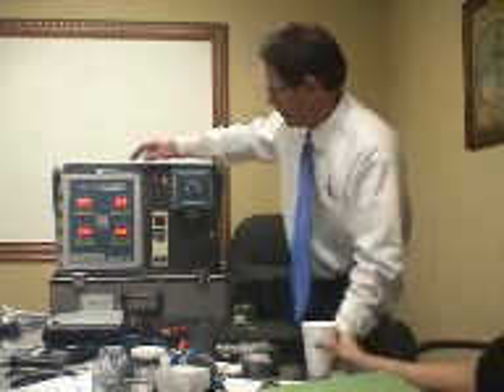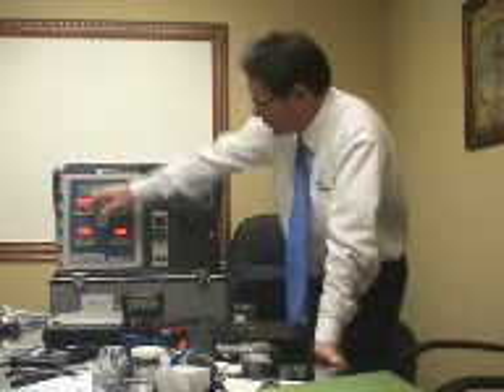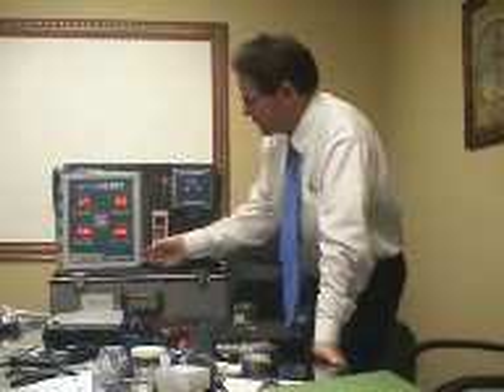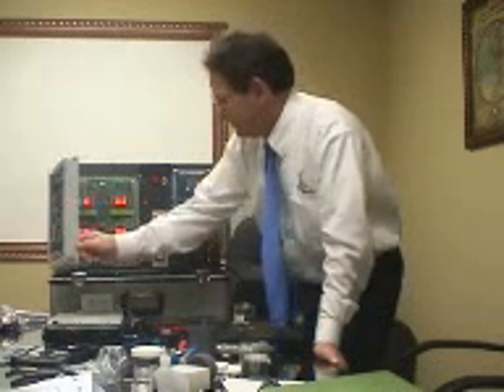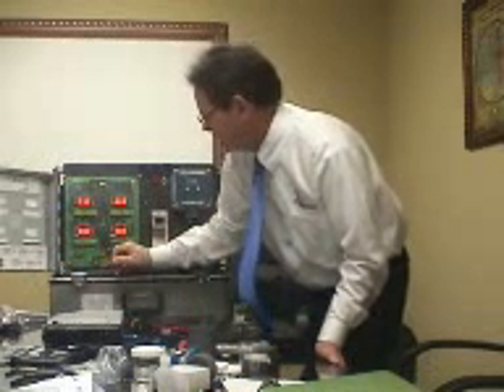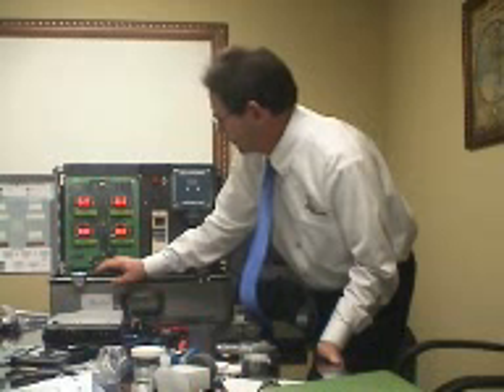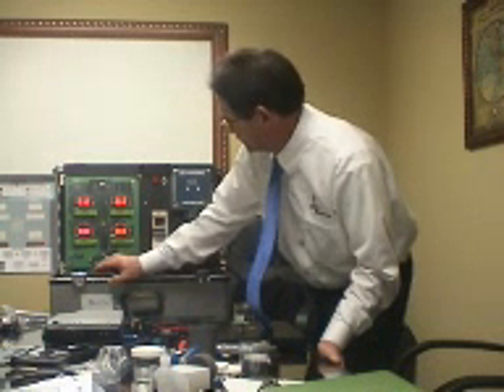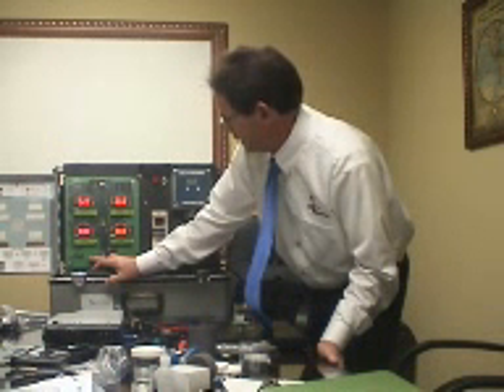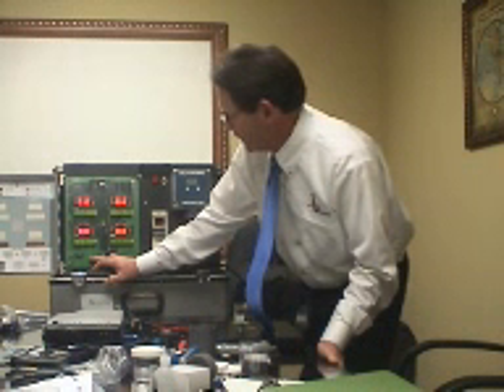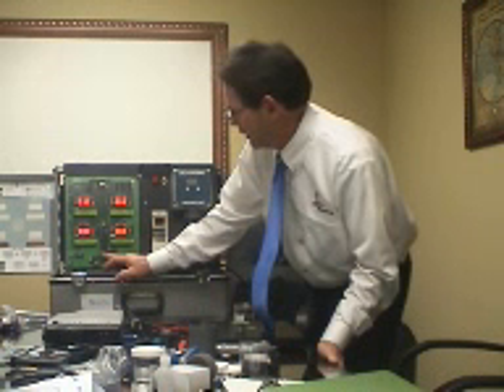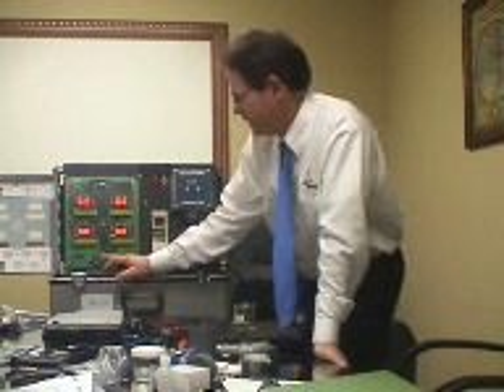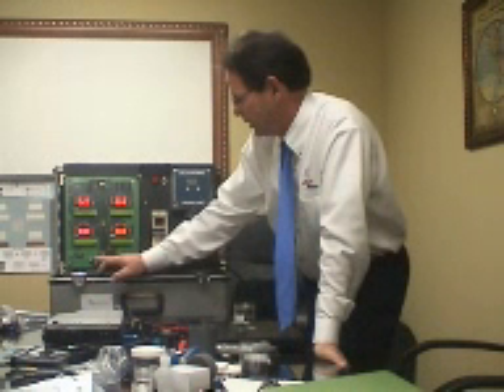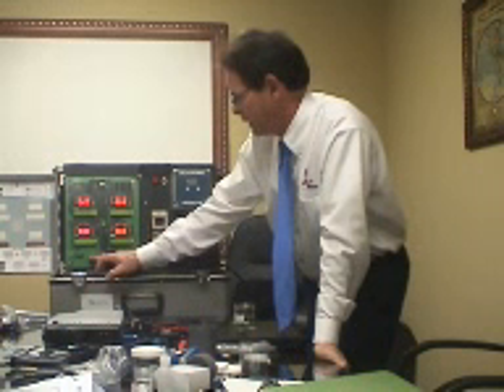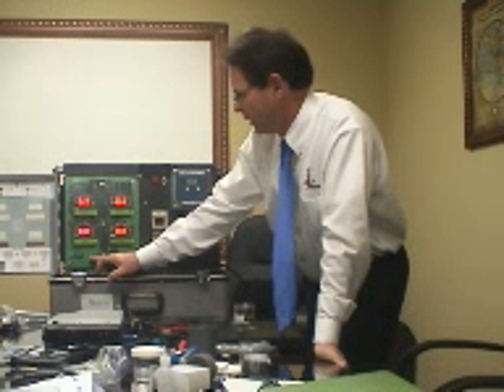21.8 is what it says right now, and we can go and align these two units. We'll go into the keys. 21.9, 22. And there's a step where you select the channel. The sensor must be reading 20.9, all right? The correct value of oxygen in the air.